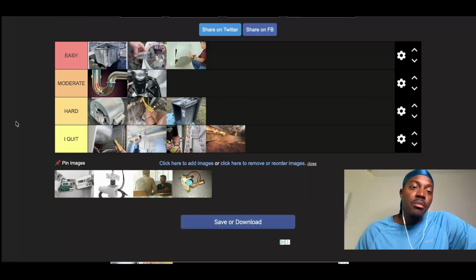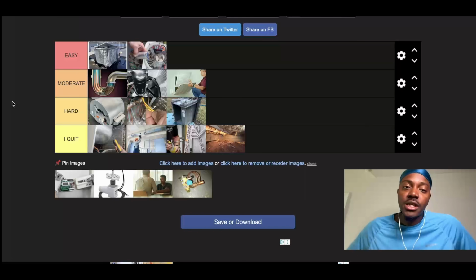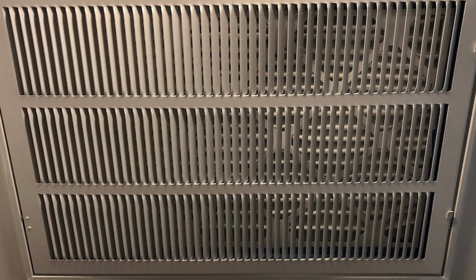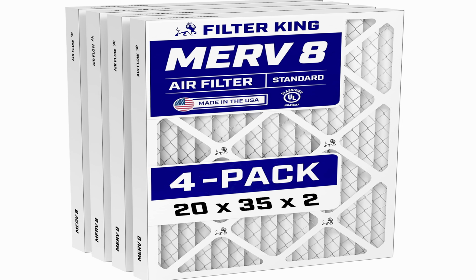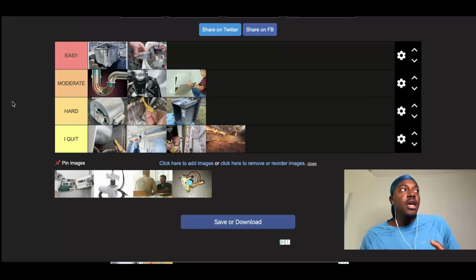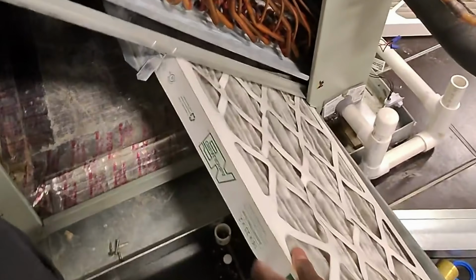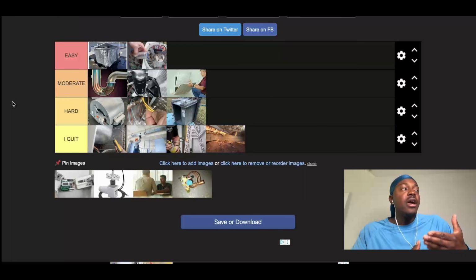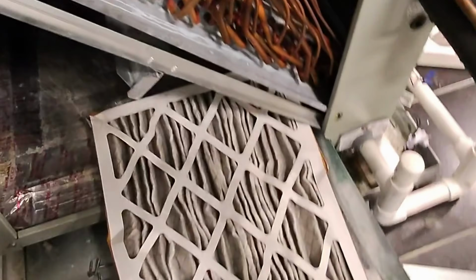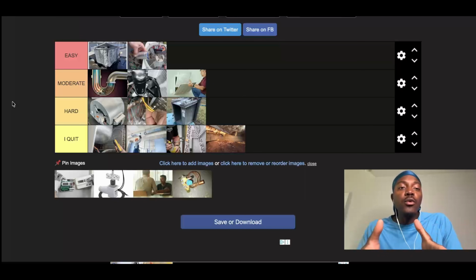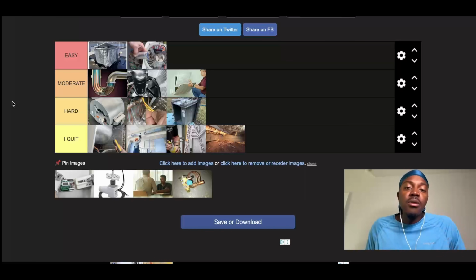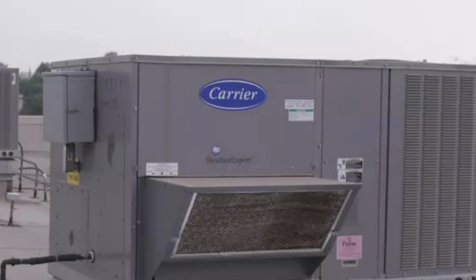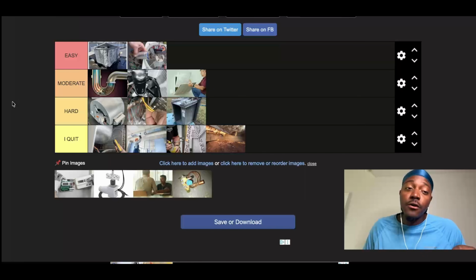Changing a filter, I'm gonna put this under moderate. And the reason I switched it is you guys are thinking about the easy ones, like you take off this return grill, put your filter in, close it, move on. But you gotta think about the other ones too. Maybe this is a skill issue for me, but when Trane has those 20 by 35 by 2 filters, when you open the filter section and try to put it into the filter rack, you really have to force those filters through in order for it to cover the evaporator coil. What sucks is that when you force it through, sometimes they break and snap in half, and now the filter is hanging off a little bit, not caught all the way on the rack to be straight. I don't know why Trane made their filter rack that way, it's kind of weird. Carrier, I love how Carrier makes their filter rack. However, putting a Carrier filter panel back on, if you've never done it before, it's gonna be very difficult for you and rage bait the hell out of you.